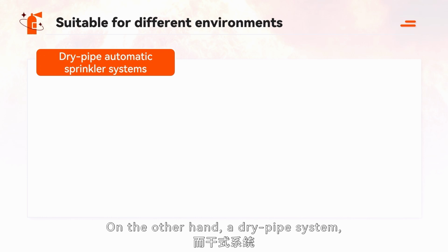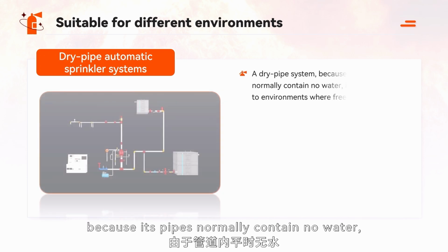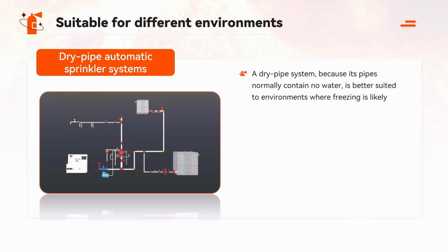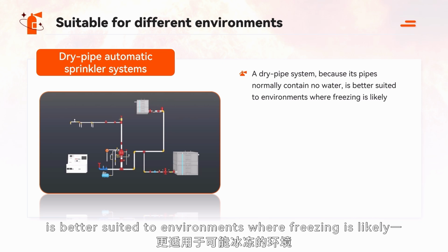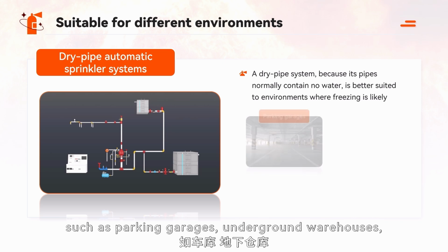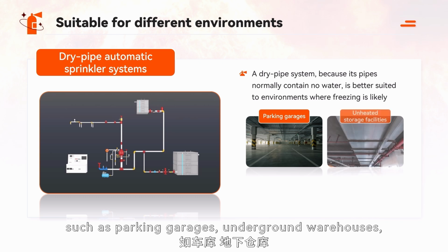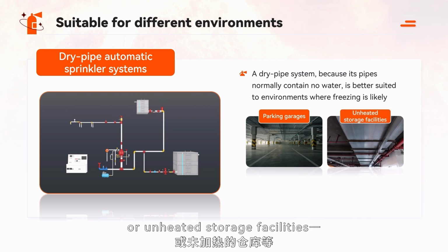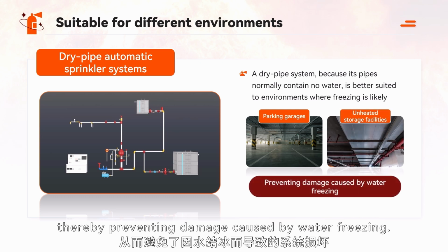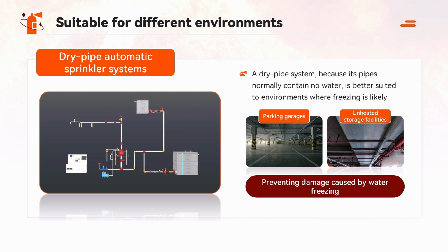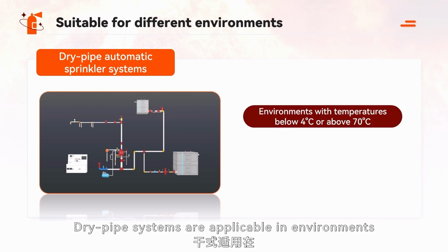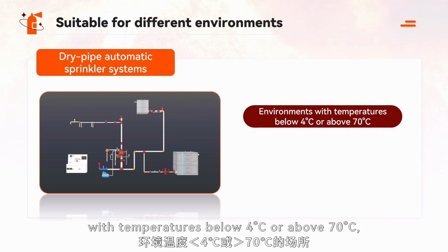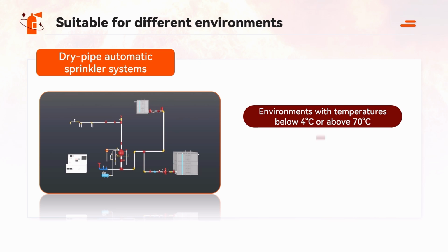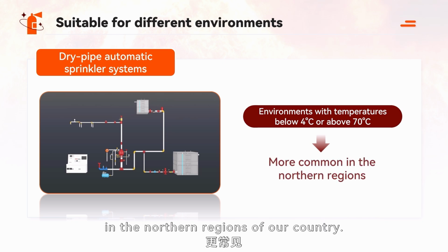On the other hand, a dry pipe system, because its pipes normally contain no water, is better suited to environments where freezing is likely, such as parking garages, underground warehouses, or unheated storage facilities, thereby preventing damage caused by water freezing. Dry pipe systems are applicable in environments with temperatures below 4 degrees Celsius or above 70 degrees Celsius, which is why they are more common in the northern regions of our country.